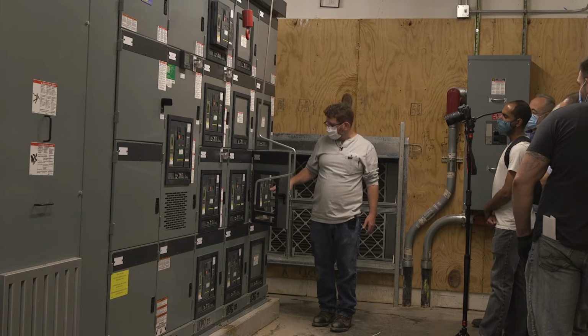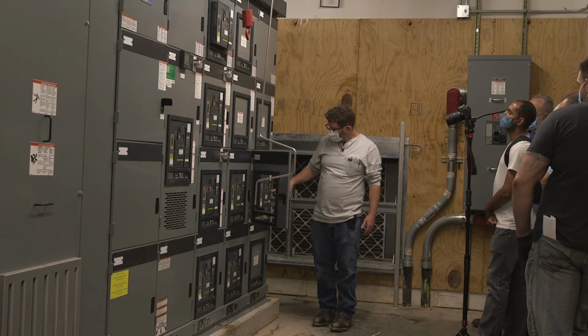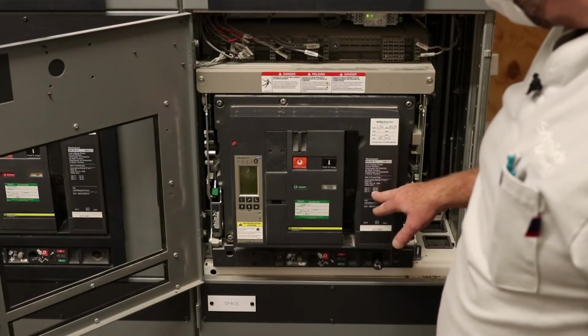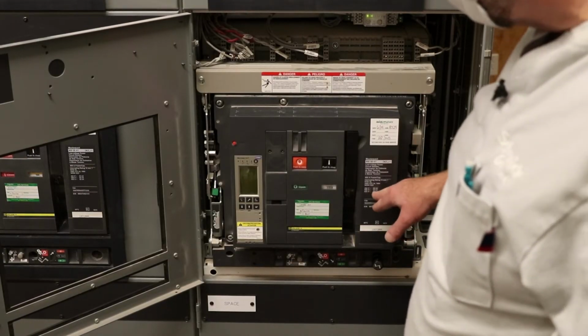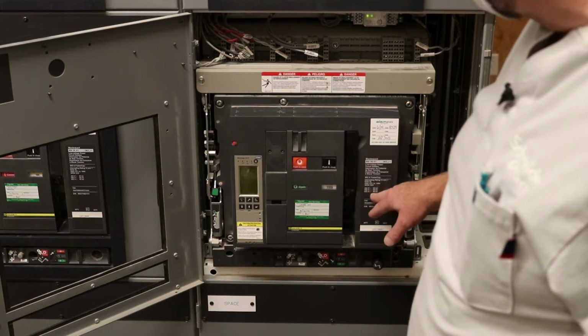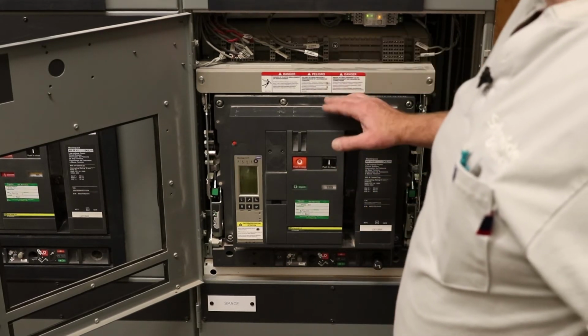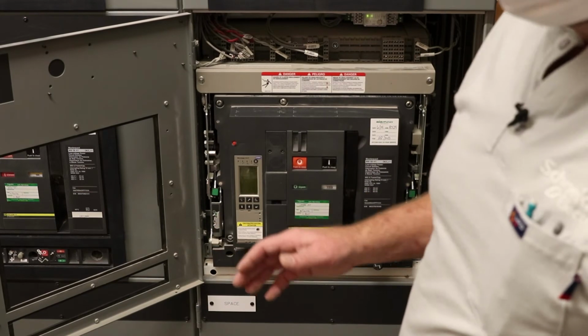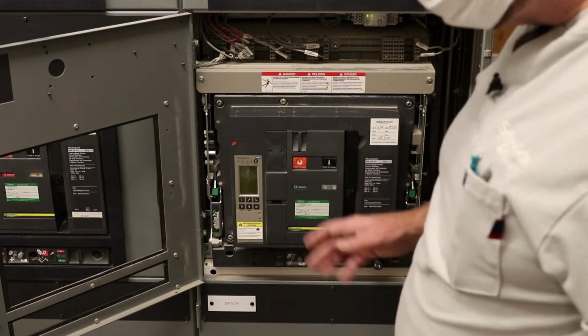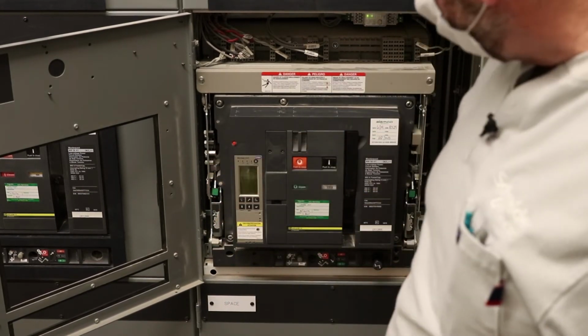If you had any other switchboards with these breakers, the other thing you have to look at is the interrupting rating. This is a 65 kA rated breaker. It could not go in place of a 100 kA rated breaker. Again, that would be a code violation. The code plates would prevent that.